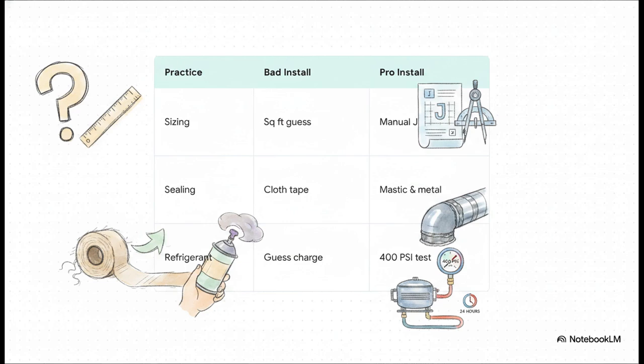And let me tell you, the contrast between a cheap, corner-cutting install and a true professional installation is massive. A bad install just guesses the size, a pro uses a Manual J load calculation. A bad install slaps on cheap cloth tape, a pro uses mastic and metal tape. But you really got to look at the refrigerant row. A bad installer will just guess the refrigerant charge.